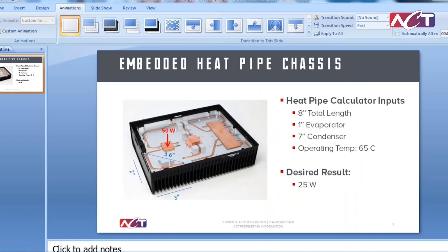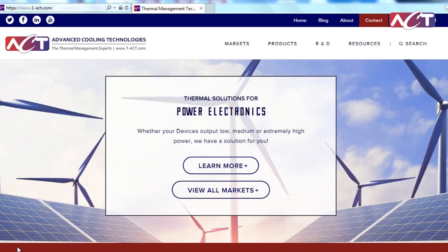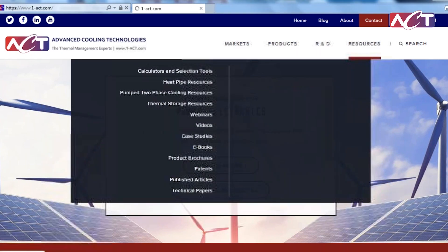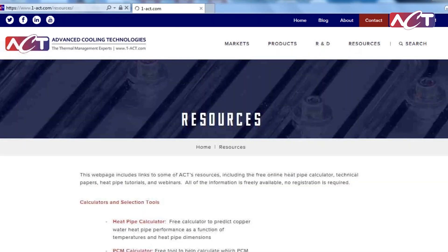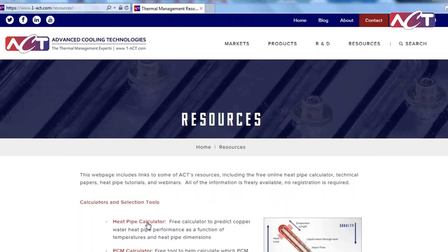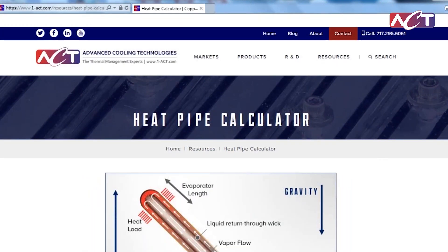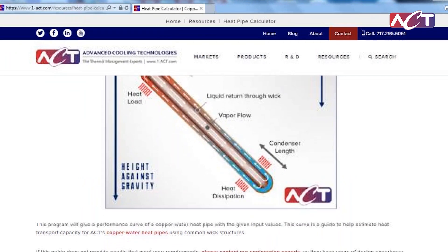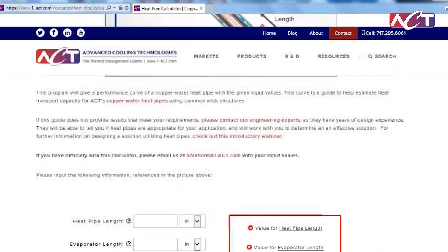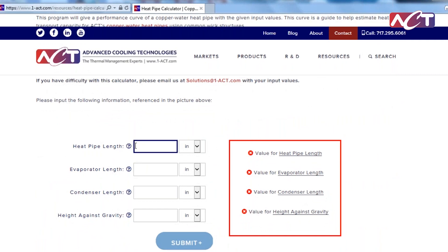Now we go to ACT's website — you can find the calculator in the Resources tab under Heat Pipe Calculator. It has a simplified diagram, but we just went through the steps to determine inputs for that specific geometry. We plug in an eight inch total heat pipe length, a one inch evaporator, a seven inch condenser, and 3.6 inches against gravity, then submit.